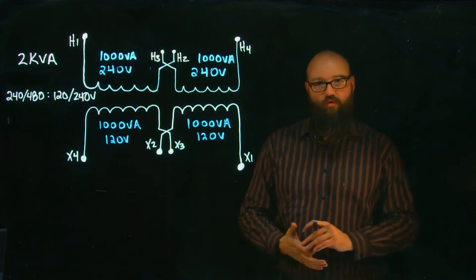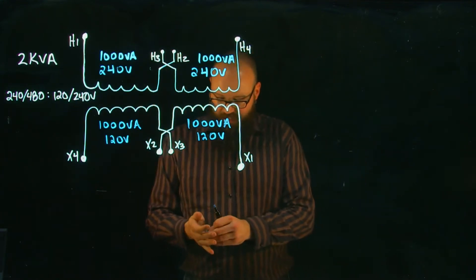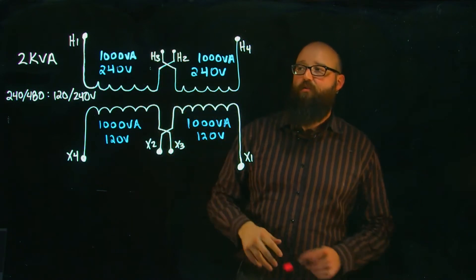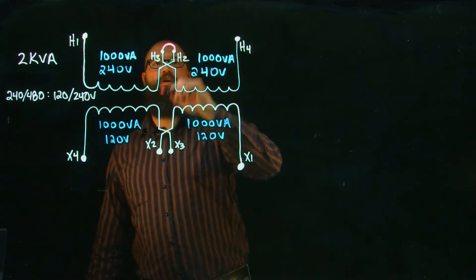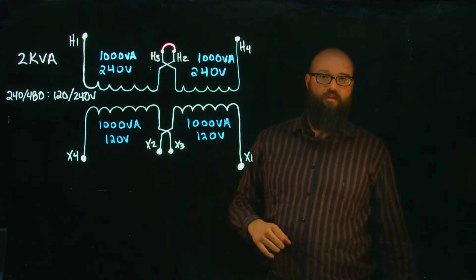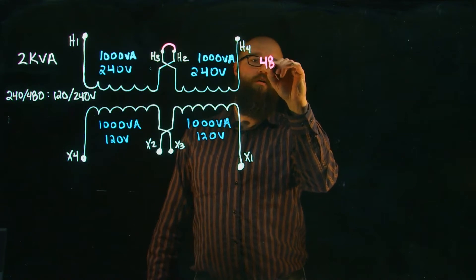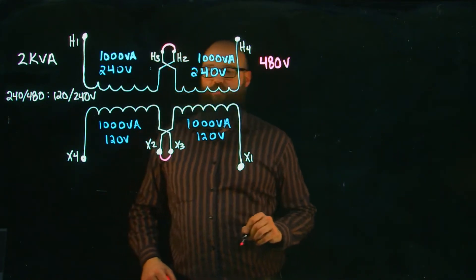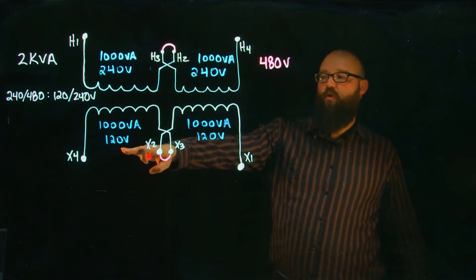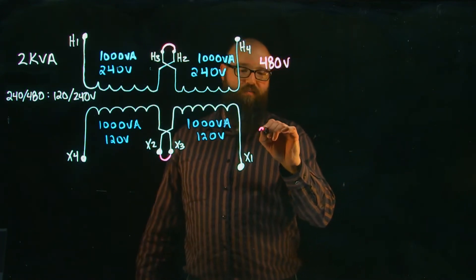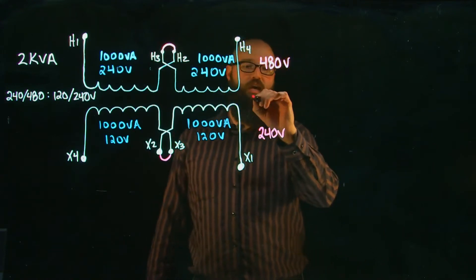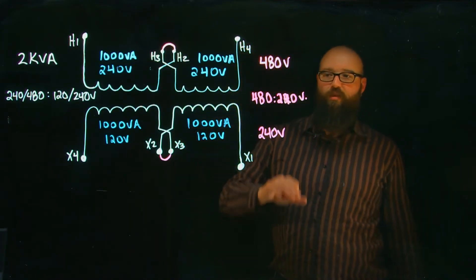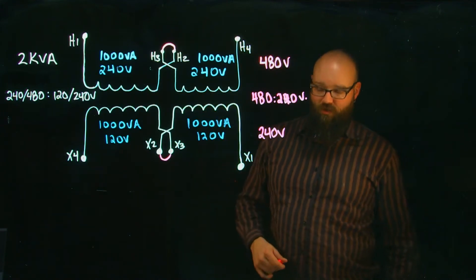It's all in the connection how we achieve the secondary voltage. If I take my primary side with 240 volts and 240 volts and connect them in series with one little jumper, I end up with 240 plus 240, giving a primary voltage of 480 volts. Doing the same on the secondary — one little jumper — gives 120 plus 120, equaling 240 volts. So that's a 480 step-down to 240 volt configuration.